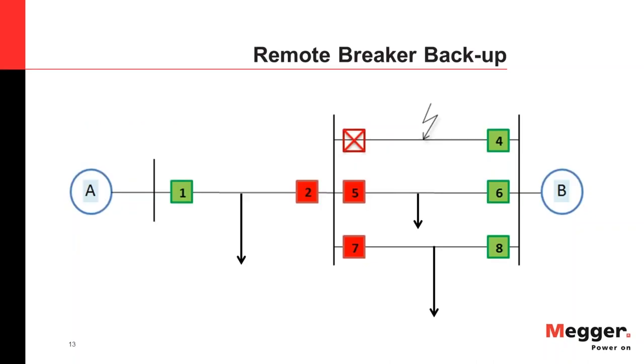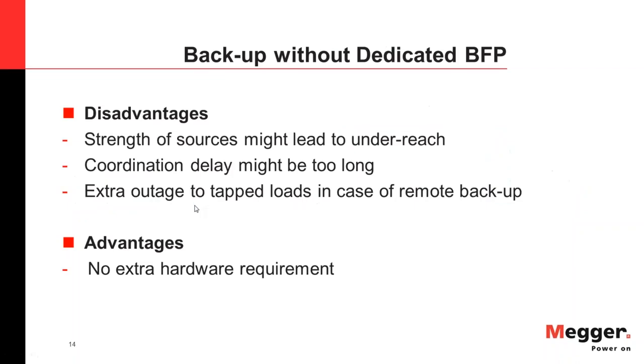This is remote breaker backup. However, consider a scenario where you have tapped loads between your generator buses and the substation bus. We will now see the disadvantages of this remote breaker backup scheme and why it is not a good option today.